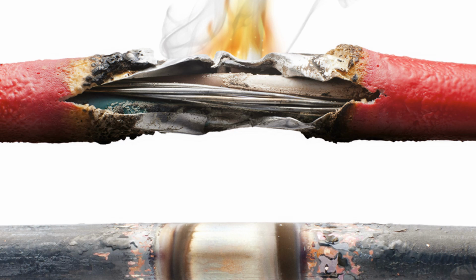Now, in the past, I've shown you guys pictures and videos of, I think there was a 7-bedroom home we went to inspect in Trasaco Springs. And that 7-bedroom home, believe it or not, was fed by a 10 mil cable, 4x 10 mil cable from the ECG pole to the home. Yeah, that's ridiculous. You probably only use a 4x 10 mil cable as the main power supply coming into the building if it was maybe a 2-bedroom apartment, for example.